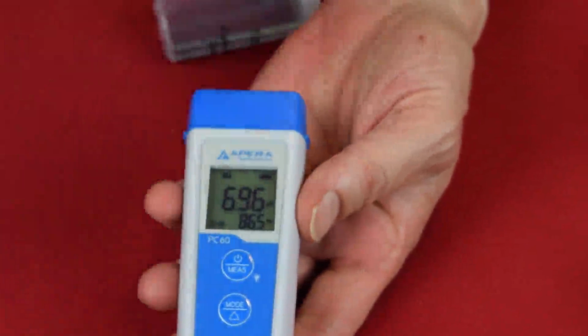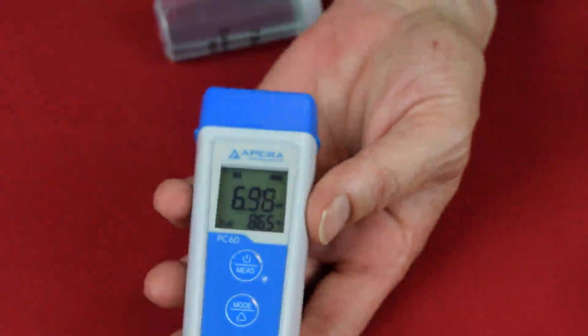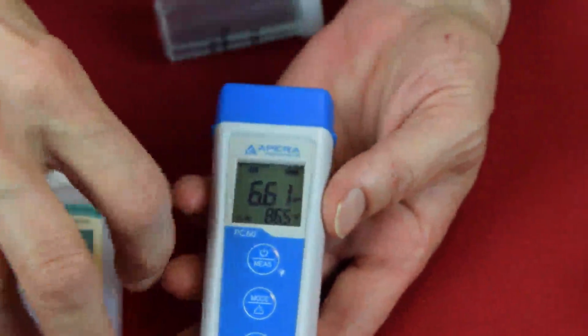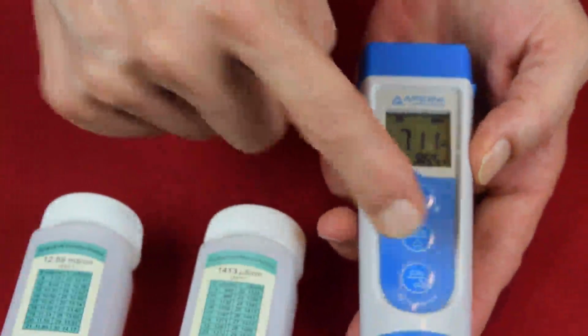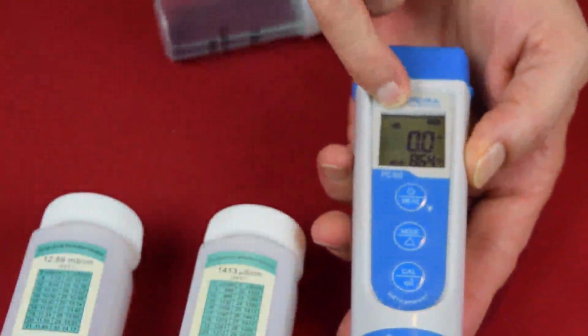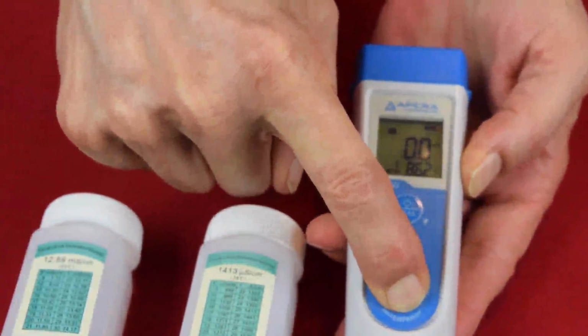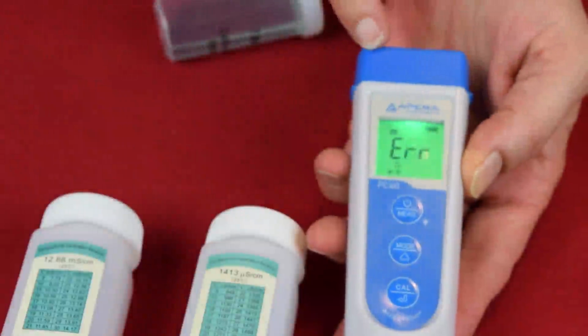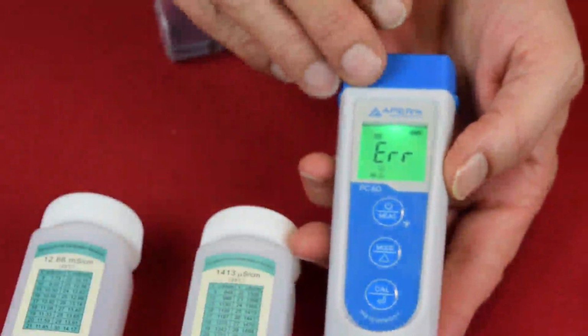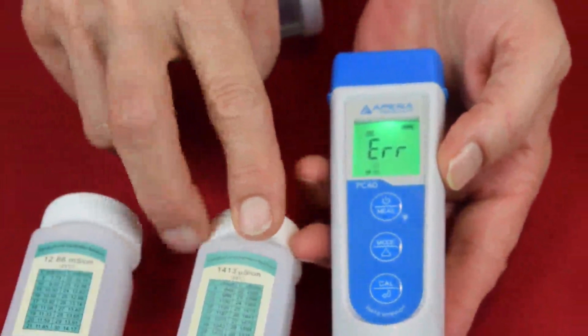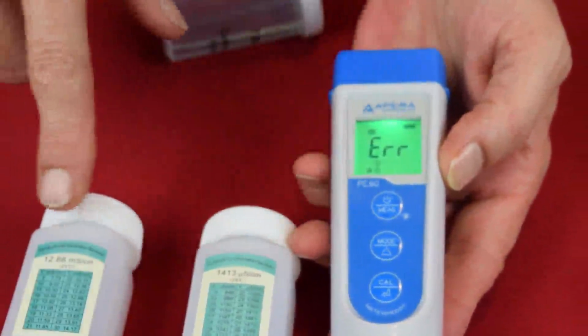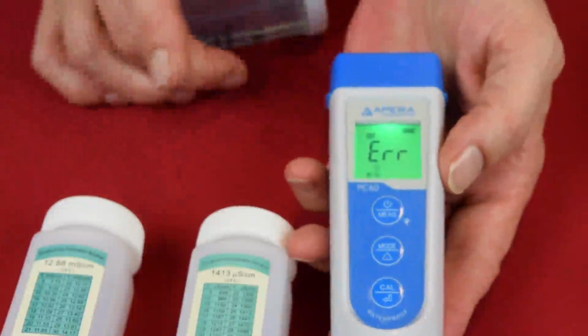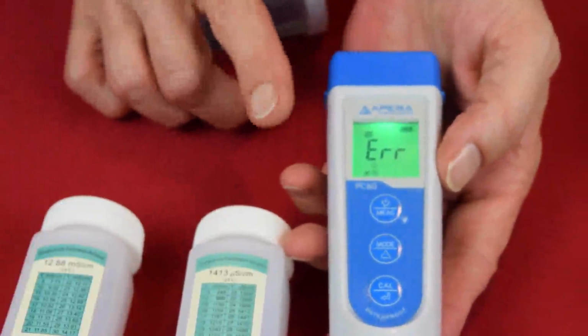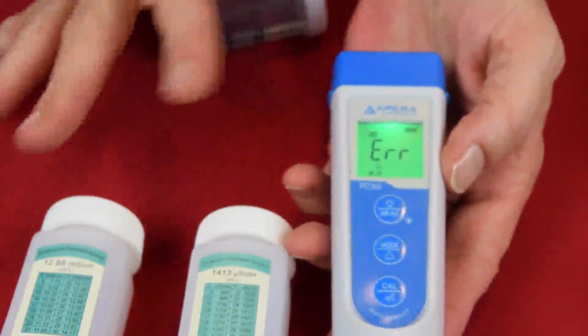And then you want to calibrate it for conductivity, which is 2 other solutions. It's this solution and this solution. So I'm going to go mode until I'm at conductivity, and then I would press down cal to take me into calibration mode. And the first one I would use would be this 1413, and then the second one would be the 12.88. You can also do 3-point calibration with the conductivity, and here you can only do 2-point because of what they give you.